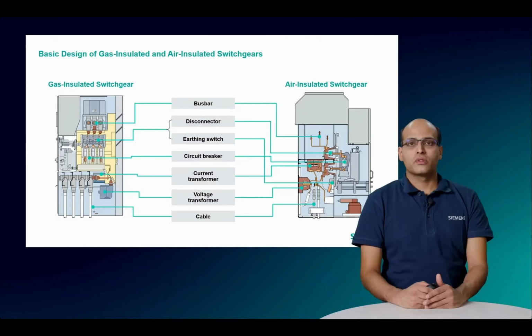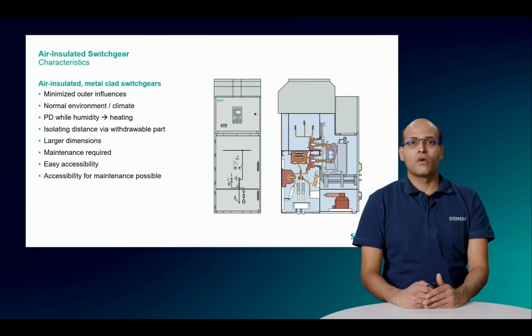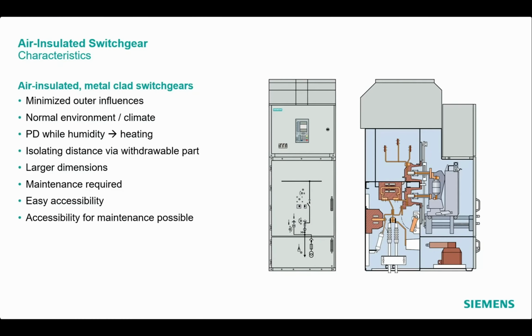Let us now begin to wrap up the session by looking into the individual characteristics of air-insulated and gas-insulated switchgears. Characteristics of air-insulated switchgears. The air-insulated metal-clad switchgears AIS use air as the primary insulating medium and are cost-effective. The metal enclosure provides a certain degree of protection against environmental factors. At the same time, the switchgears are more vulnerable to external environmental conditions such as pollution, moisture, and saline environments. These factors could affect the dielectric strength of the switchgear. This can lead in some cases to issues like partial discharge, which can lead to overheating and to further failures.